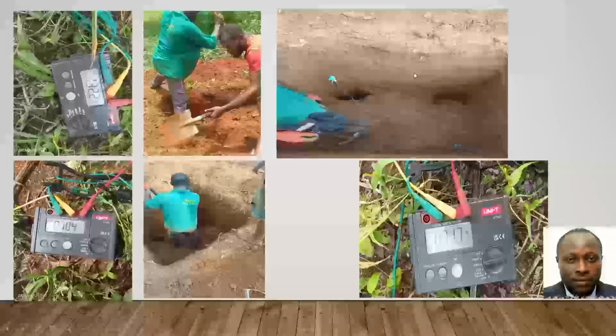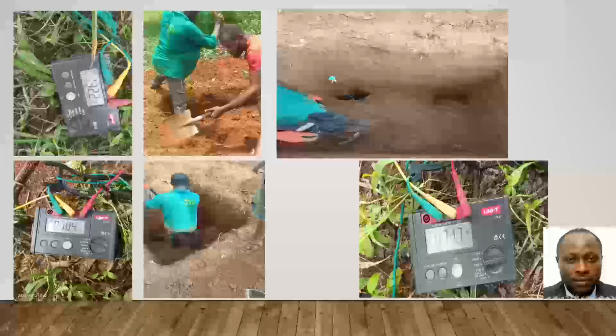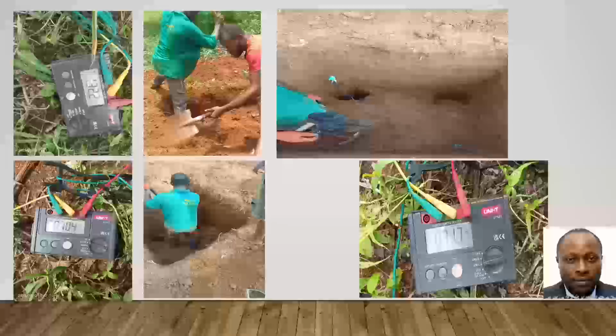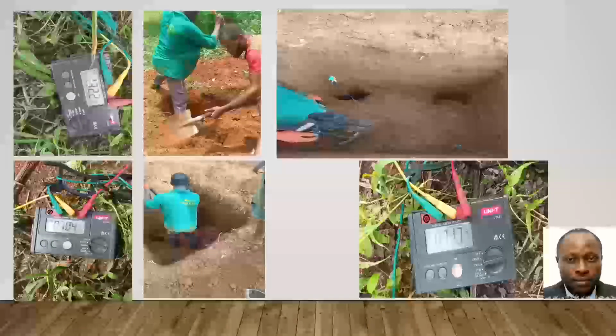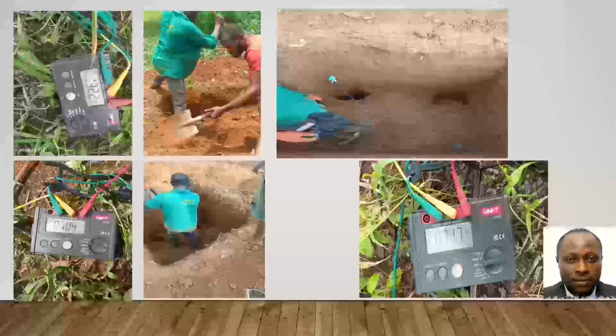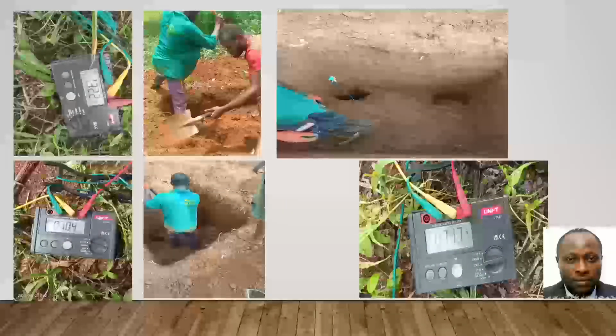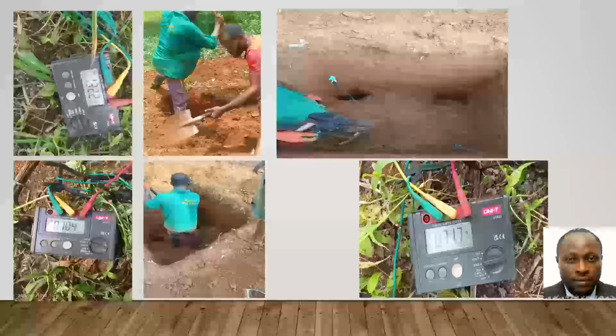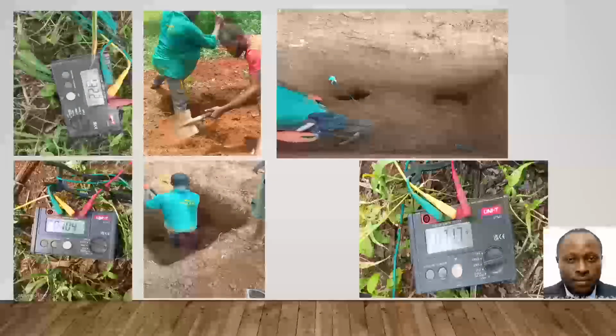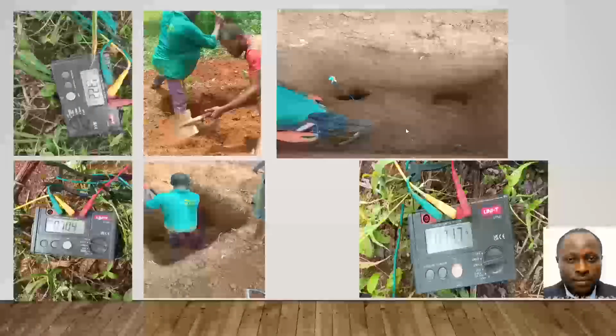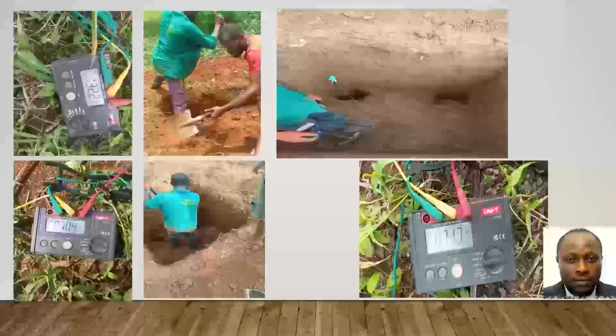When you get to the middle, it's a little bit soft. When you come down, you meet the rock. So the installation here is the type we are looking at. It's no more going to be vertical, it's going to go horizontal. So the design here: we do a vertical until we hit the rock, we bury the copper rod, then we come to these 4 feet around where this man is standing, and begin the horizontal design on it. By combining everything together, we'll get the desired result.